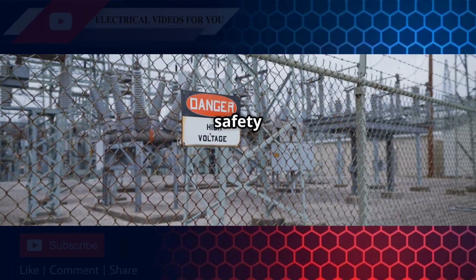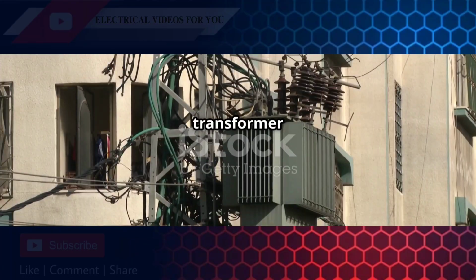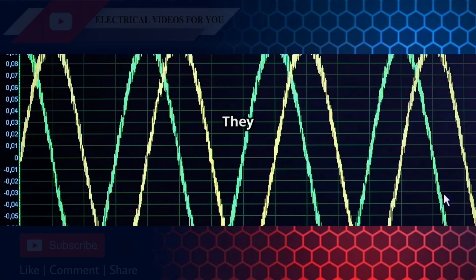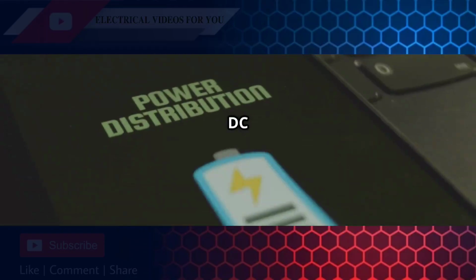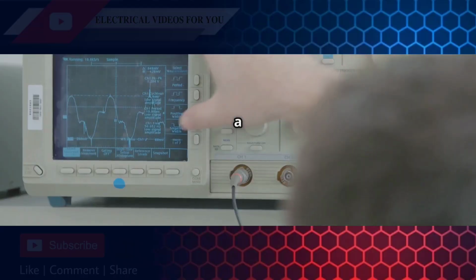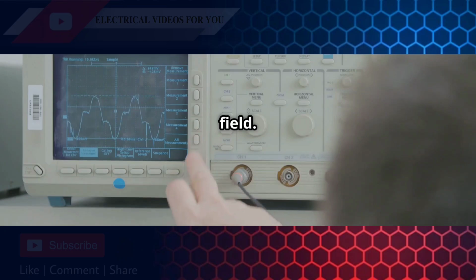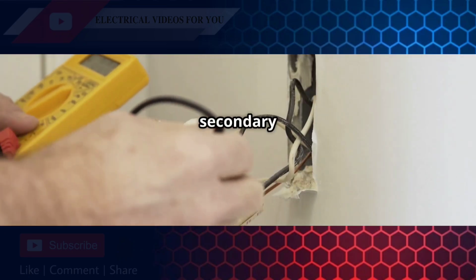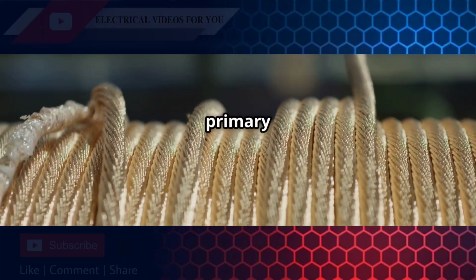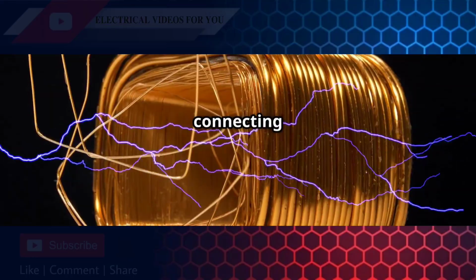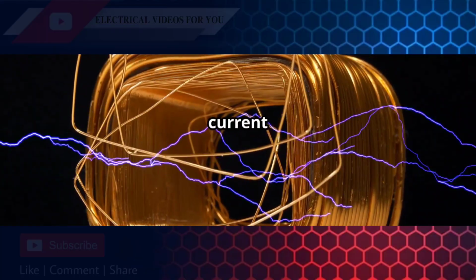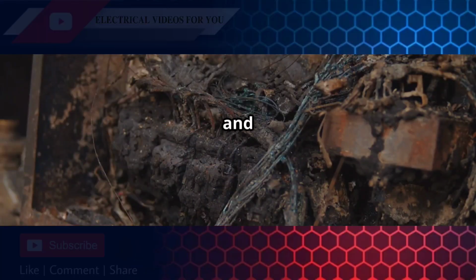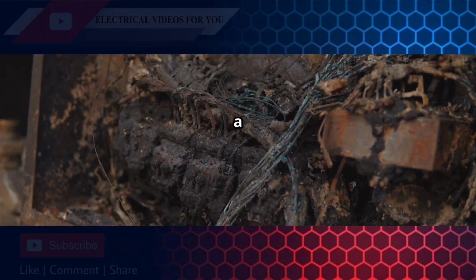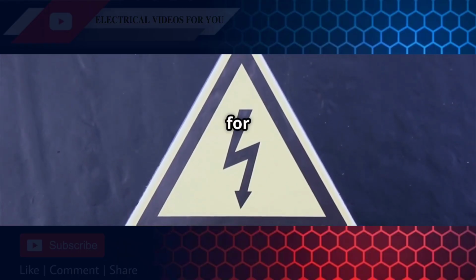Here's a very important safety tip. You can never ever connect a transformer to a DC supply, like a battery. Remember how transformers work. They rely on a changing magnetic field, which is created by an alternating current. DC flows in only one direction, so it creates a steady, unchanging magnetic field. This steady field can't induce a current in the secondary coil. Even worse, the primary winding has very low resistance, so connecting it to DC would cause a huge amount of current to flow, quickly overheating the coil and destroying the transformer, possibly causing a fire. So remember, transformers are for AC only.